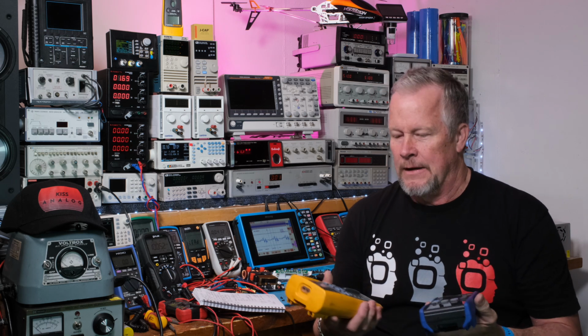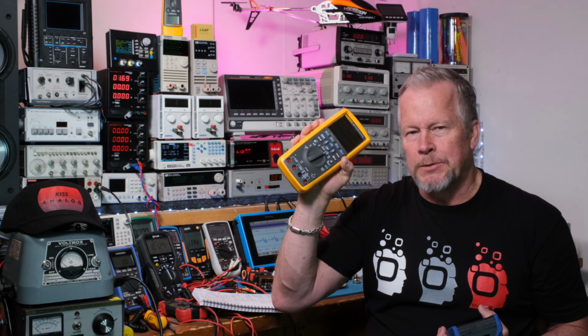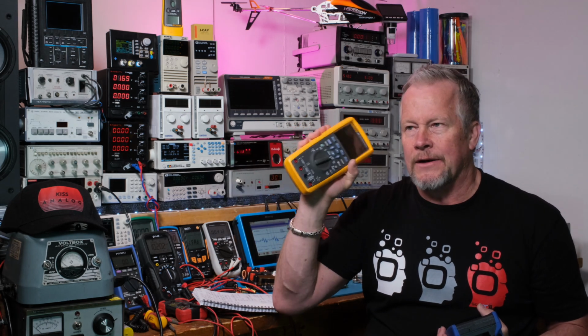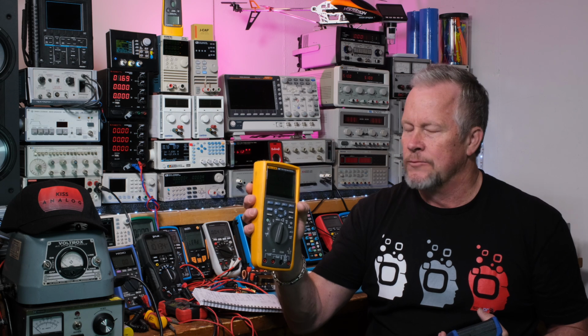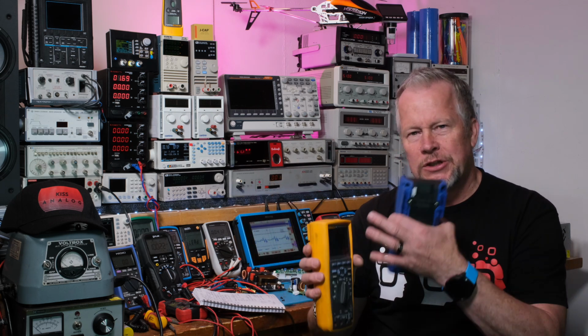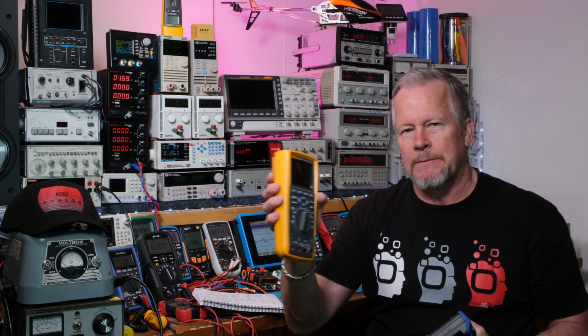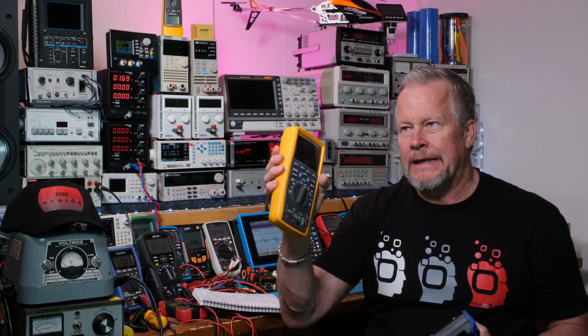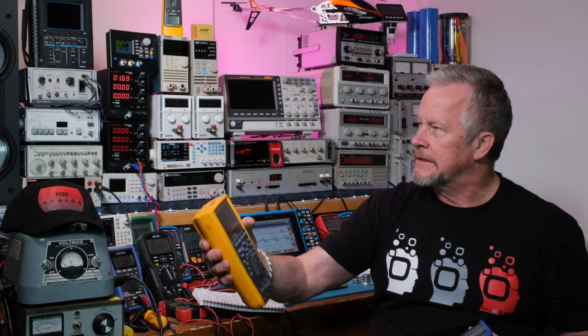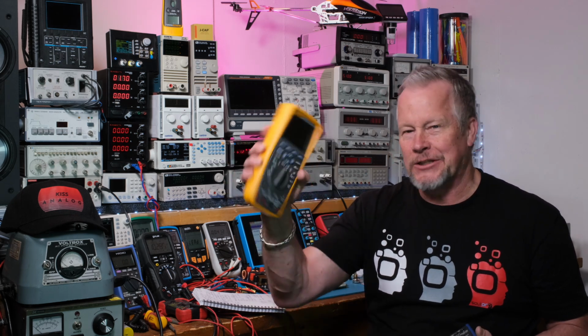So, all right, battery life. I guess that's kind of part of build quality, maybe, I don't know. But battery life, I think this was supposed to be improved, so it's supposed to last 100 hours and 200 hours in data logging, which is interesting. In data logging mode, it must shut down other functions and go into some low power mode. That was nice they did that, because if you are trying to log something and you walk away, you don't want to come back, see your battery died, and wonder how many points you logged. It says I can get to 10,000, but I got half of those before the battery died. So 200 hours, that's good.